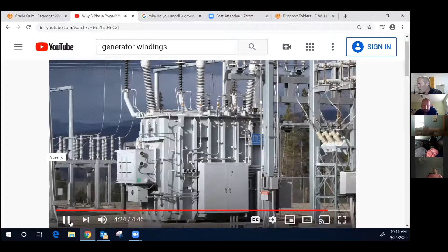With 12 phases, there would be 12 circuit breakers and 12 bus bars. So the complexity of coupling it—it's called a high phase order line—into a substation sort of defeats the economics of it. Although periodically people raise the question, because it would be possible, for example, to couple from 12 phases through a transformer down to 3 phases. But it remains an intriguing concept, probably more useful for power educators than for transmission line companies.